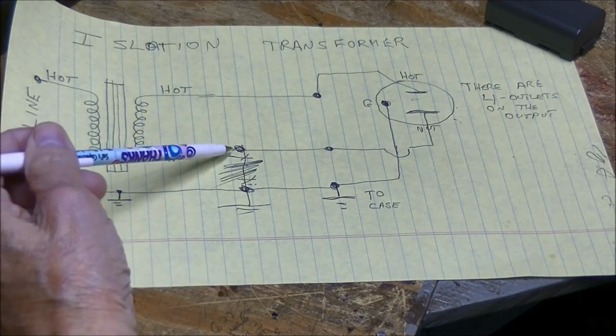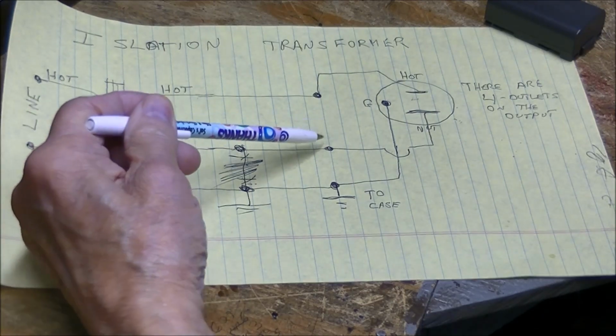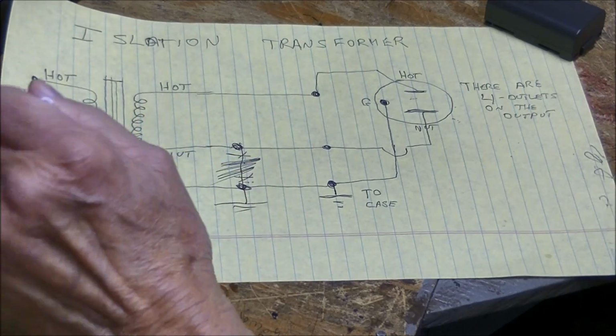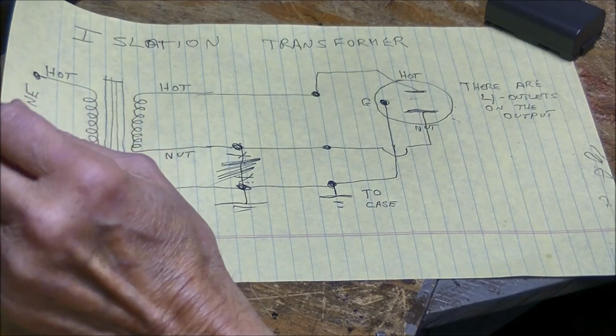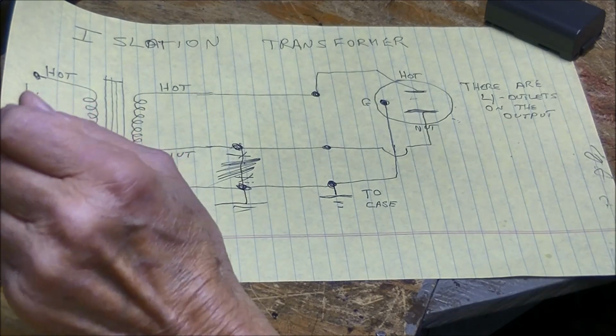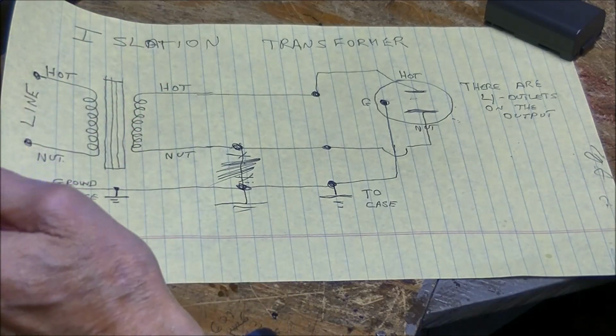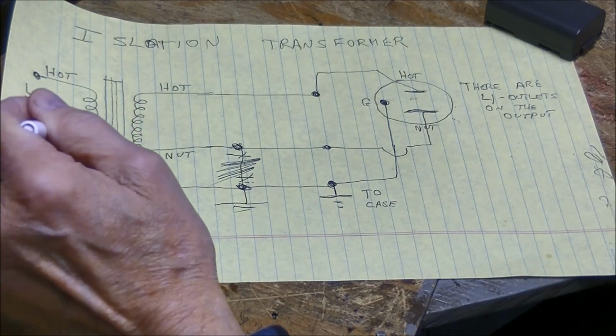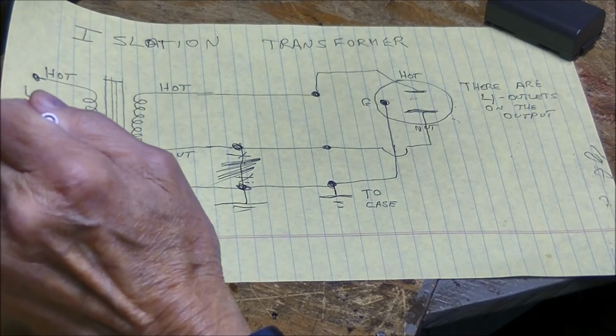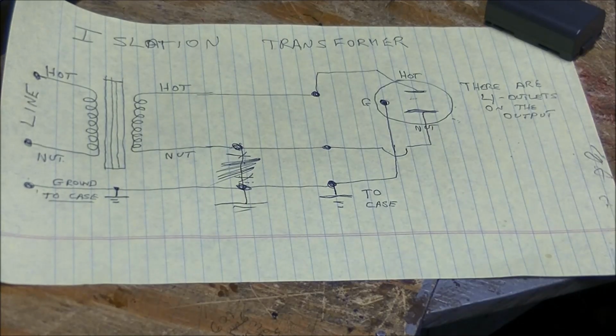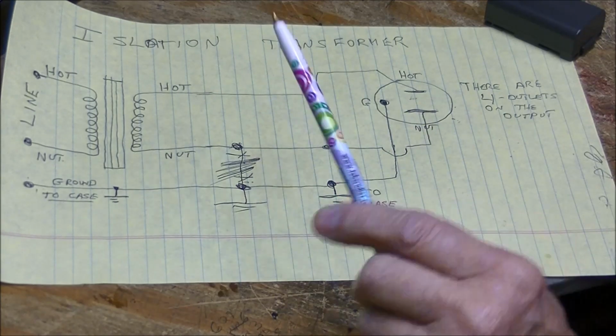However, if you did not remove this bond, this neutral was grounded to the case, which is in turn grounded to the ground wire, which goes back to the power line, and also the power panel, which is also shared and grounded at the bonding point at the electrical panel. So your ground and your neutral are grounded at the electrical panel at your house. I think I explained myself very thoroughly. I want to close this subject. I had to make this because every once in a while I've been getting comments on it, and they're telling me it's incorrect. Please study what I'm trying to tell you.